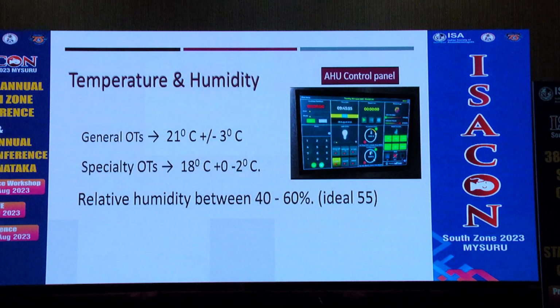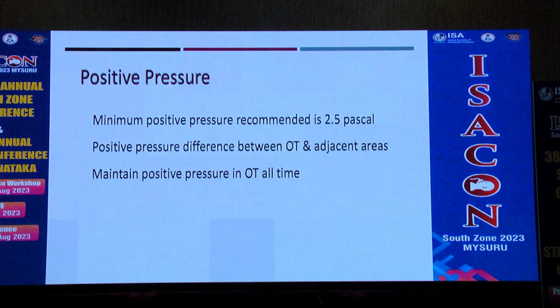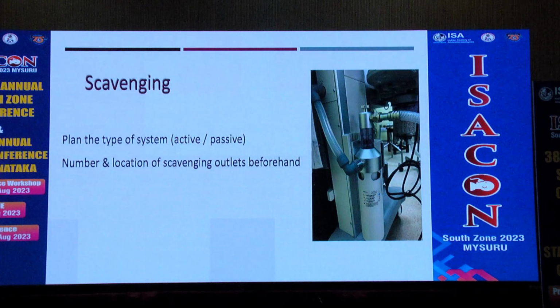As for specifications for temperature and humidity, the specialty OT has a lower temperature of 18 degrees and the general OT has 21 degrees, and relative humidity ideally is 55. The recommended minimum positive pressure in the OT is 2.5 Pascal, and the pressure difference should be maintained throughout between the OT and the adjacent areas. And there is scavenging. There should be either an active or passive system; it is a must. This should be planned in the initial designing stages, including number and location.